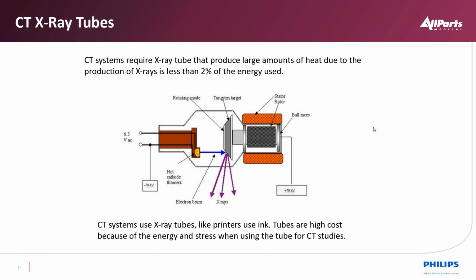So one of the things that we deal with is X-ray tubes. X-ray tubes are not very efficient. If we put 100 kW in, we get 2 kW of X-ray out, and 98 kW of heat. As we talked about earlier, when we went from a single slice scanner to a 4-slice scanner, where we had 20 mA for 1 second, now we would need 80 mA for a 4-slice to have the same dose.